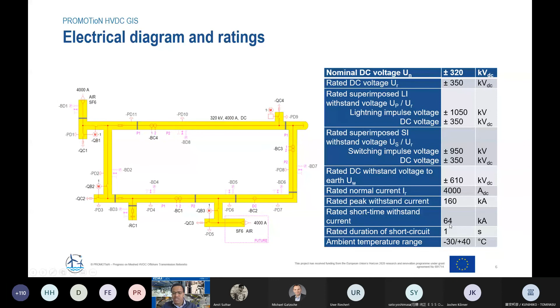The whole GIS is rated for 4,000 amps of DC current, and there are also short time currents with standard specification. Here you see 64 kA, for example, for 1 second, and the operation range is between -30 and 40 degrees Celsius.